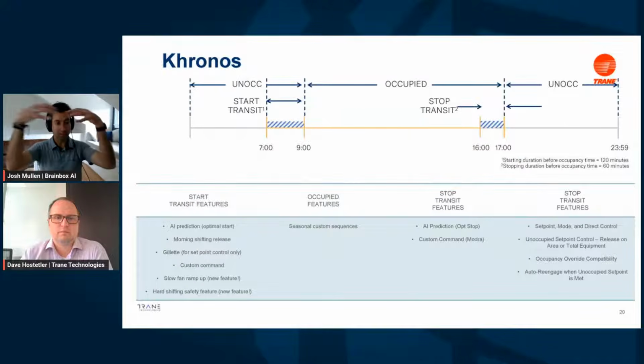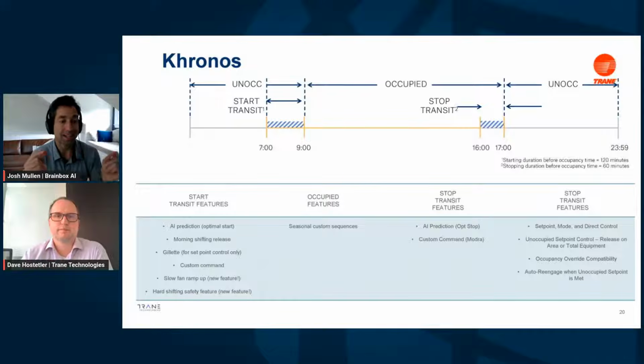And how that all gets pulled together is I went through how we're able to leverage the space temperature predictions. So those space temperature predictions are put into our algos. One of our algos is Khronos. It's really focused on optimum start and optimum stop. It's taking that space temperature prediction for each and every zone. Let's say for a multi-zone VAV system that has electric heat and a rooftop unit. And it's using those space temperature predictions to figure out when to start, which VAVs it should operate first and pull on or hold off for a little bit longer, when to turn the system on as a whole, and then how much reheat should it turn on and at what time. And the same is happening at the end of the day. It's seeing how long it can drift the building for and still meet ventilation requirements or whatever the guidelines that the customer has for us.